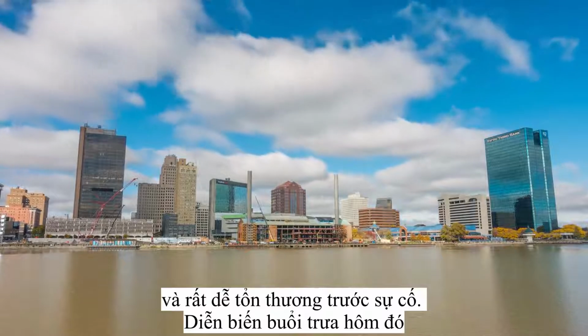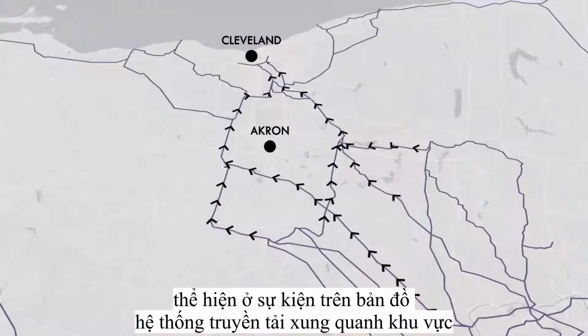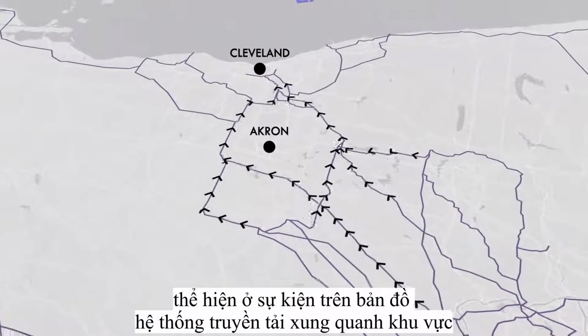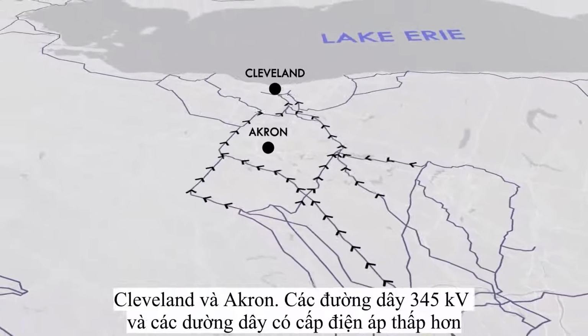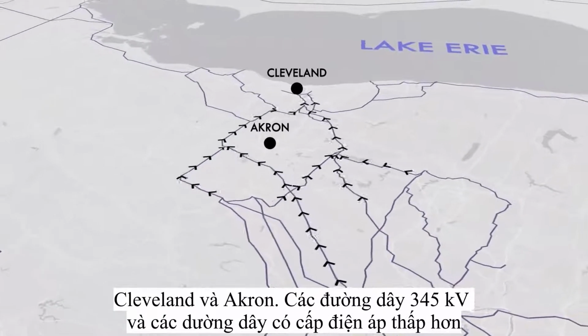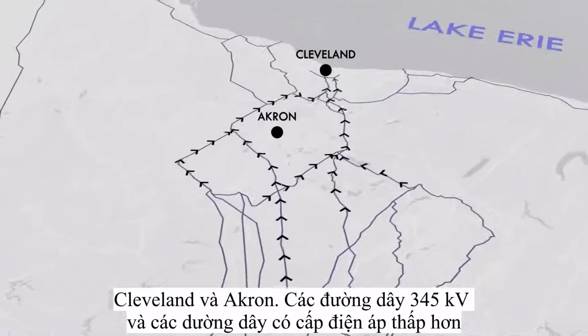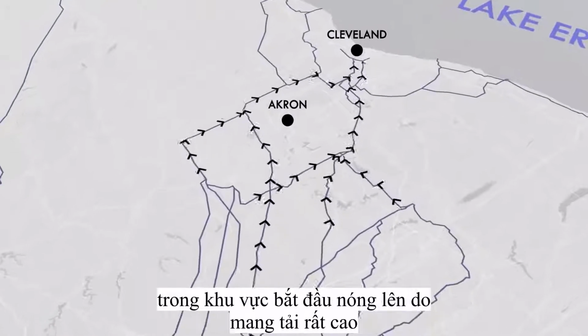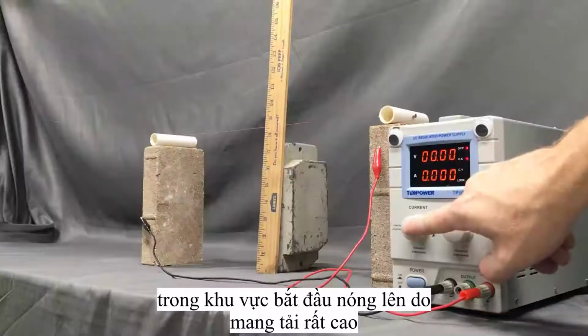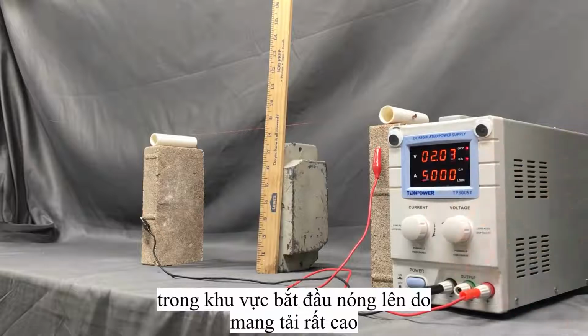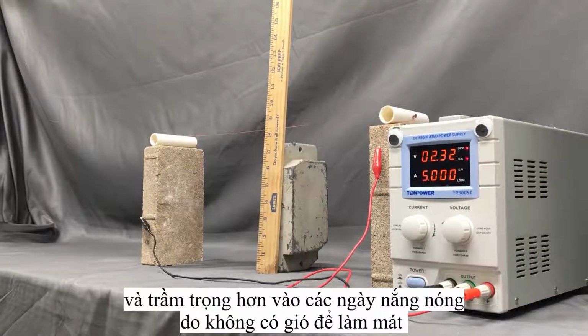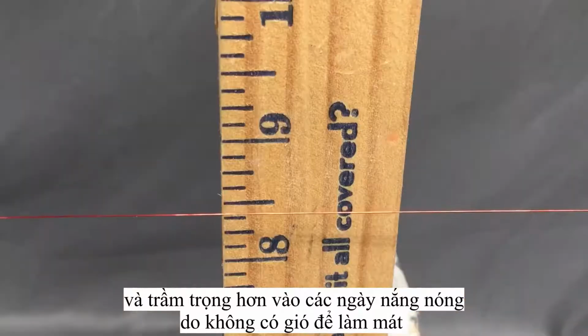And the afternoon was just getting started. I'll show the next events on this map of the highest voltage transmission network around Cleveland and Akron. These are only the 345 kilovolt lines, but there are lower voltage transmission lines in the area as well. Transmission lines heat up as they carry more current due to resistive losses, and that's exacerbated on still, hot days when there's no wind to cool them off.